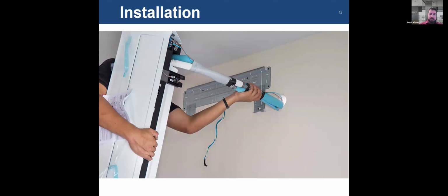This is just kind of what you would see when installing a wall-mounted unit. This person's already connected their drain lines. They've already connected their power and communication lines, and now they're pushing the whole unit through the wall. Once everything is through, you'll clip it on the bracket, snap it in place, and then you'll make your refrigeration connections outside the wall. It's typically on the exterior. It could be on an interior wall. It could even be in between the wall or in the wall cavity. But typically, for an existing installation, you're on the exterior.